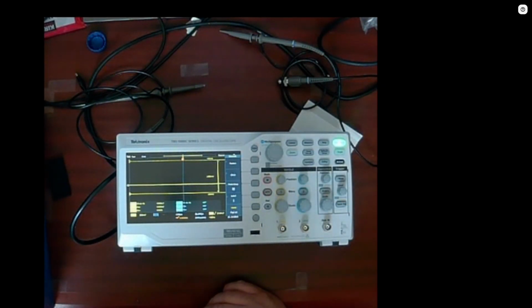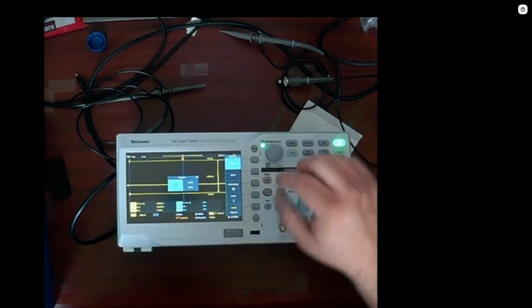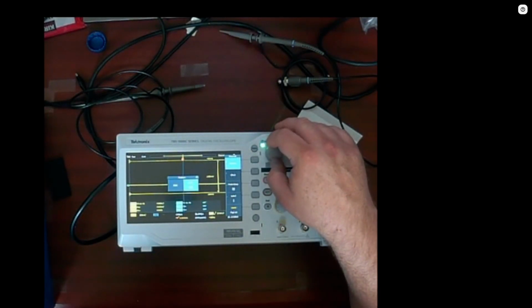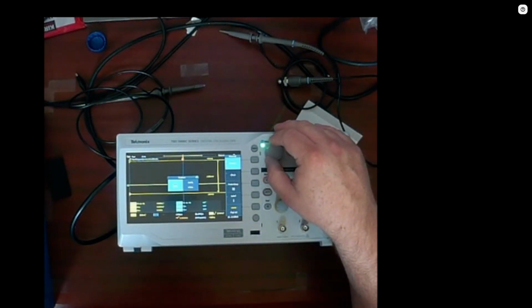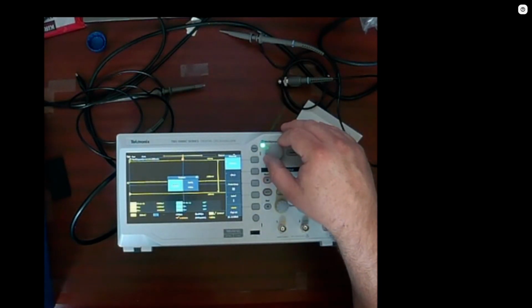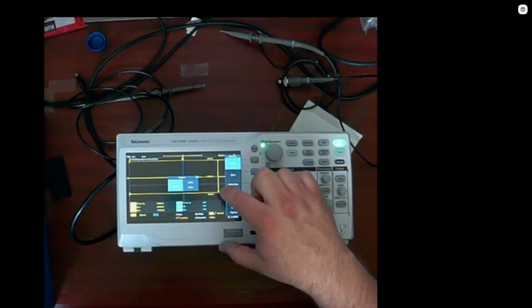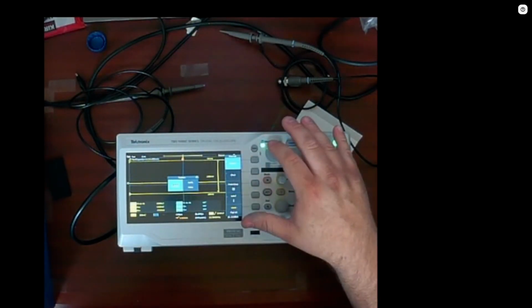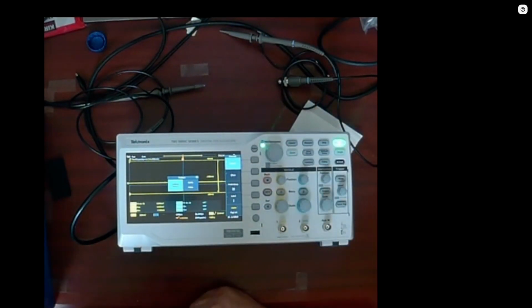This is going to be how you'd set up and describe what your waveform is. So your position. The position is going to be this, where is your center line? So when you light that up, you can set it up to, I want to go number of divisions, or I want to set it to a specific number of divisions. So we're going to go to the divisions, use the button to select it, and then as we slide it up, as you can see, my center line for that waveform is now moving. So now if I want to move my waveform up and down, because maybe I have a really, really high positive or a really, really low negative value, I can shift the center line around to be able to display it on my screen. So there's kind of the options for that.